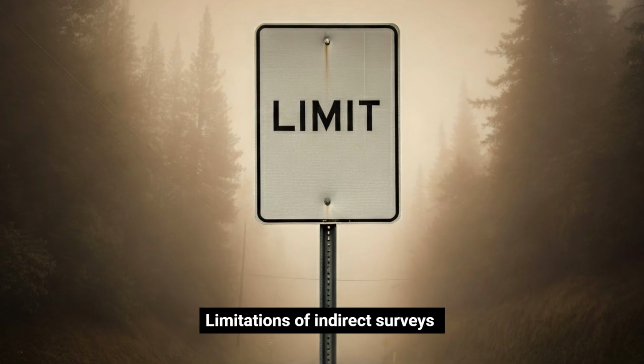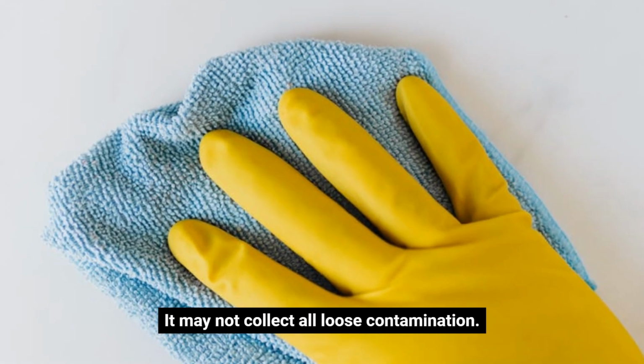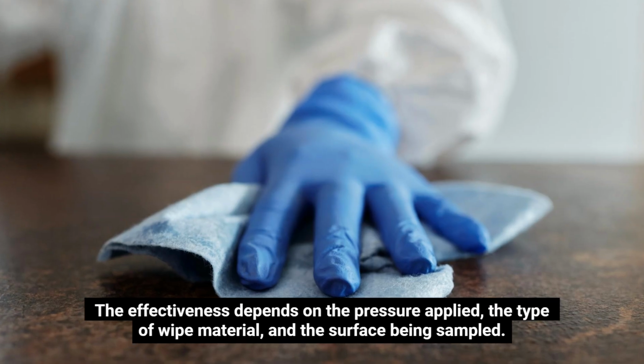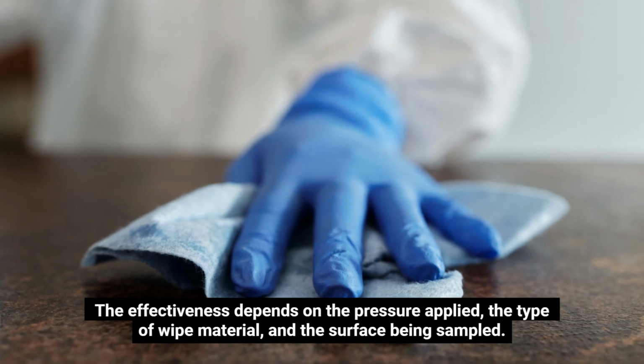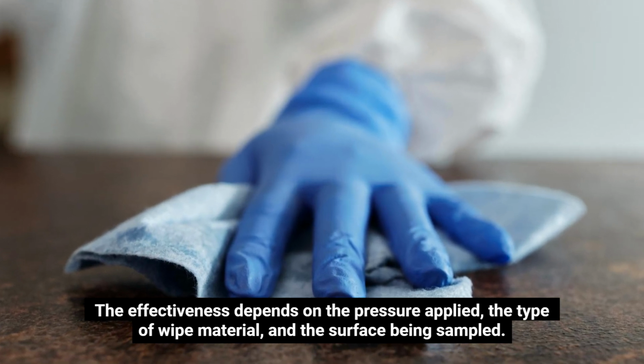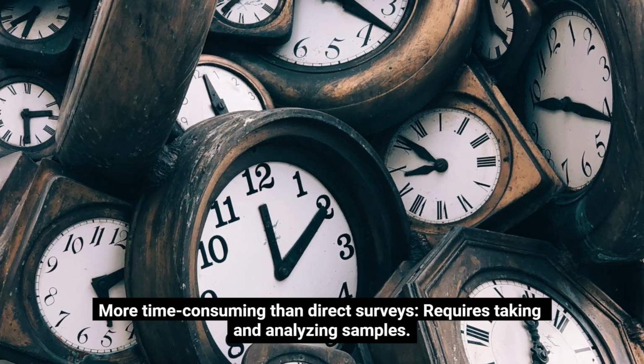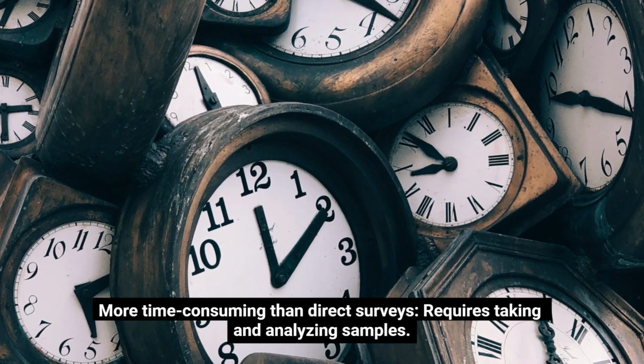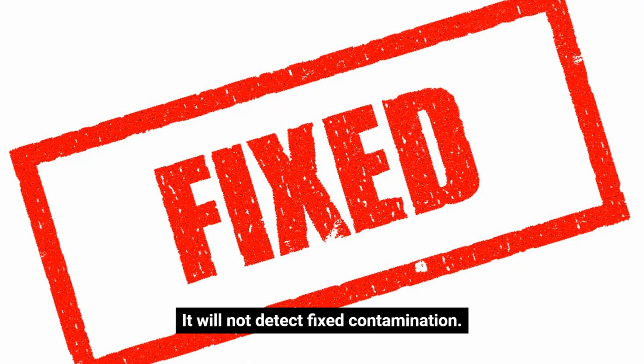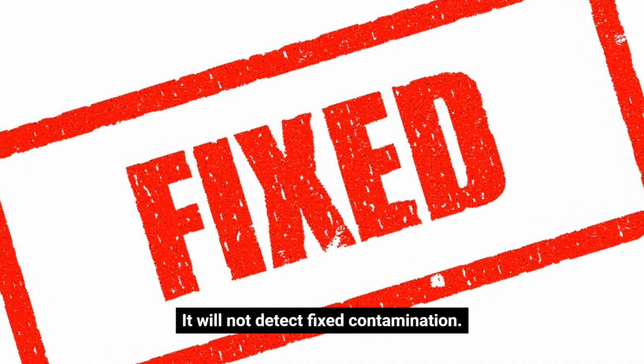Limitations of indirect surveys. It may not collect all loose contamination. The effectiveness depends on the pressure applied, the type of wipe material, and the surface being sampled. More time-consuming than direct surveys. Requires taking and analyzing samples. It will not detect fixed contamination.